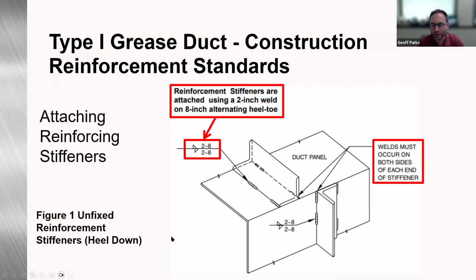Also in this duct construction grease duct reinforcement standard, we have details for attaching the reinforcing stiffeners. Figure 1 is an unfixed reinforcement stiffener, heel down. A couple of things to point out: you want to use a 2-inch weld at 8-inch alternating heel-toe spacings. And the welds must occur on either side of that angle, on each side of the stiffener.